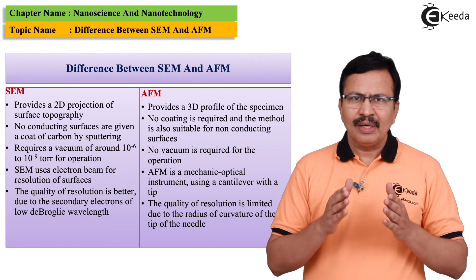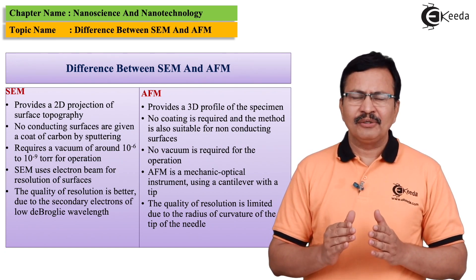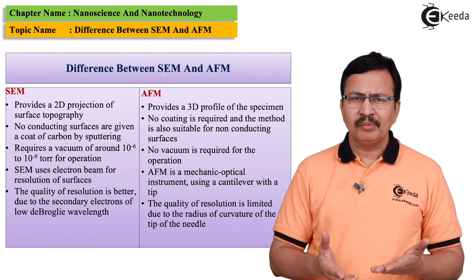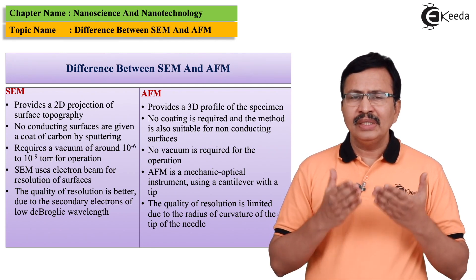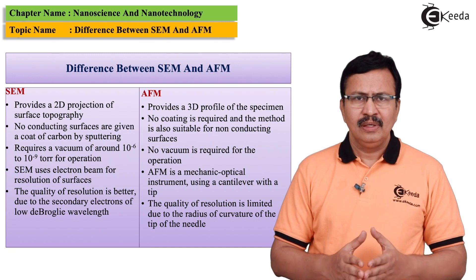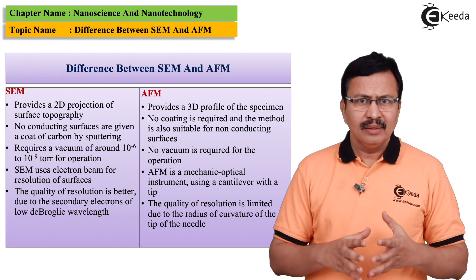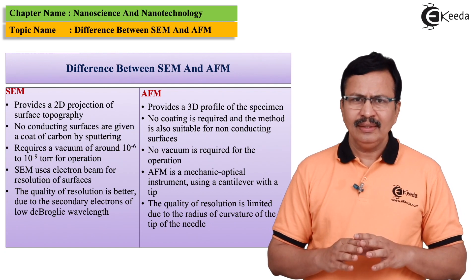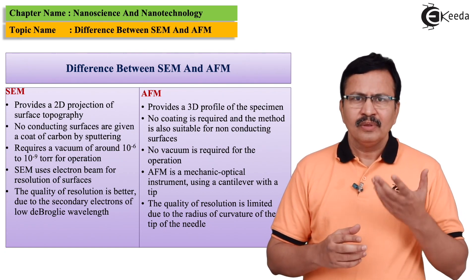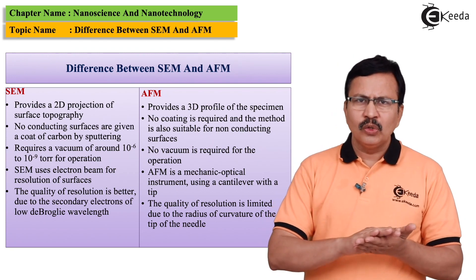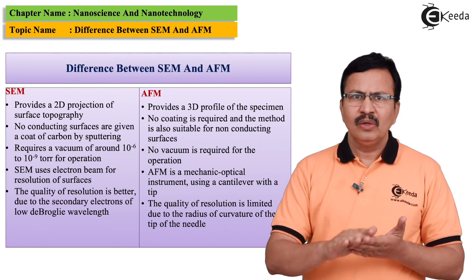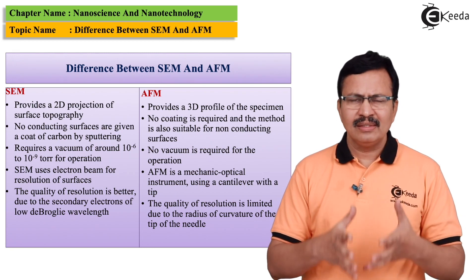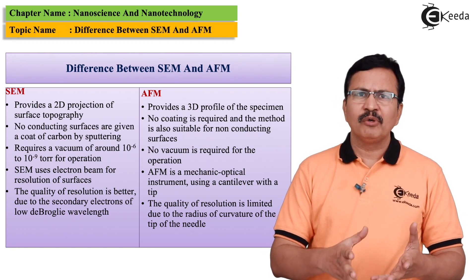Coming back to SEM — the scanning electron microscope — in the case of scanning electron microscopes, we need conducting samples. Does this mean that we cannot analyze a sample which is non-conducting? We can definitely do that. By giving a coat of carbon on a non-conducting surface, we can actually analyze these surfaces too with the help of SEM.